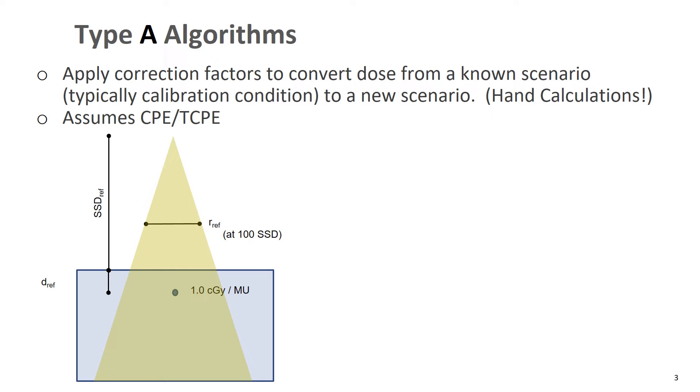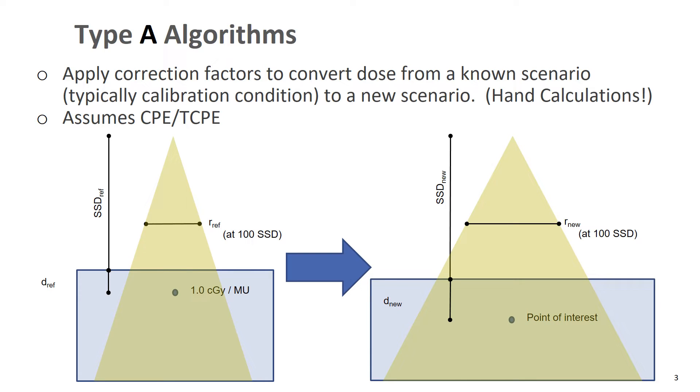And at that particular location, we know that we have one centigray per monitor unit. We know what the dose is because we calibrate the machine to give that. It's measured. And then we want to calculate dose to a new condition. Maybe it has a new source to surface distance, maybe it has a new depth, maybe it has a new field size, and so forth.